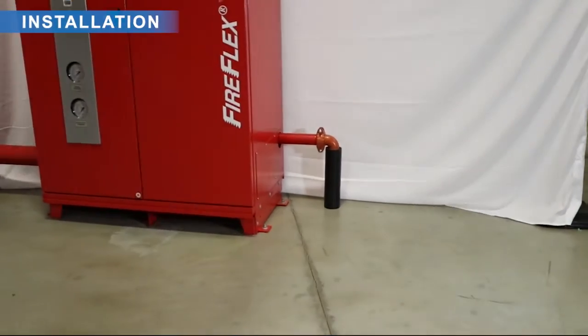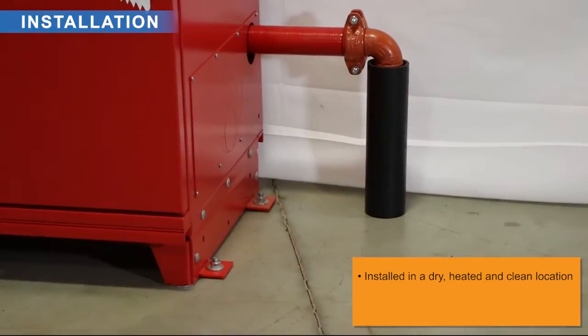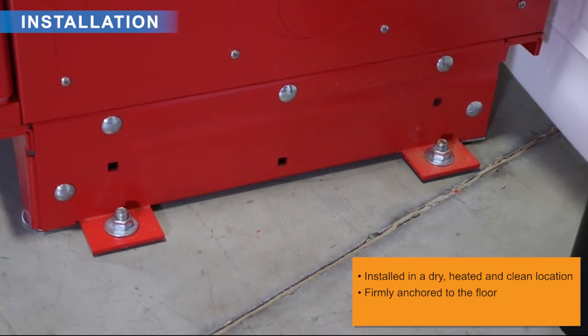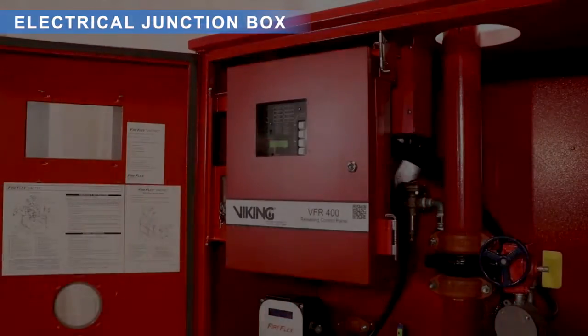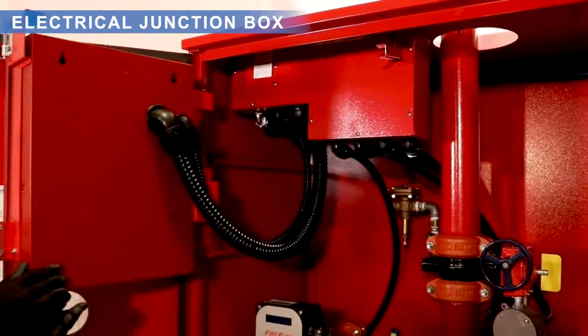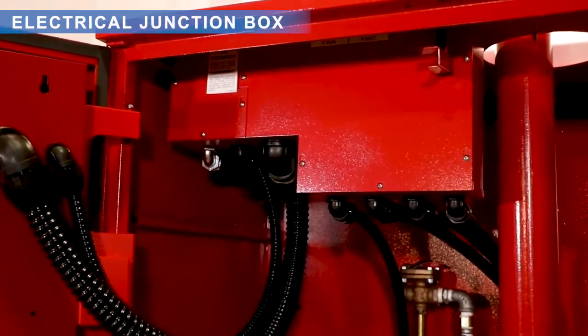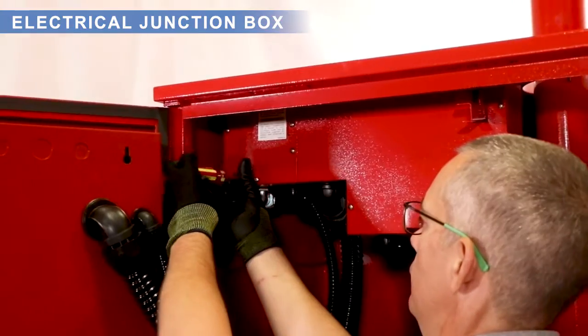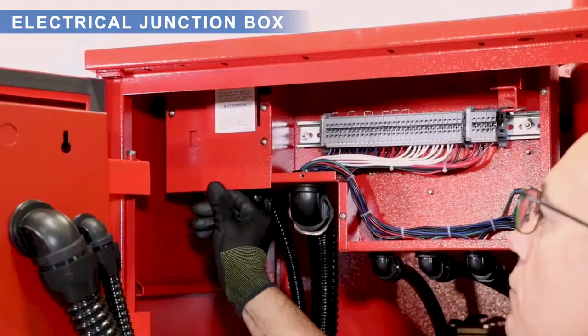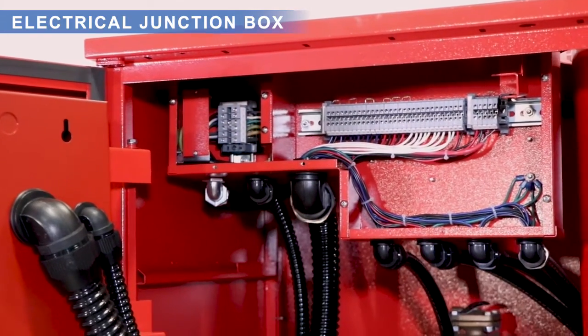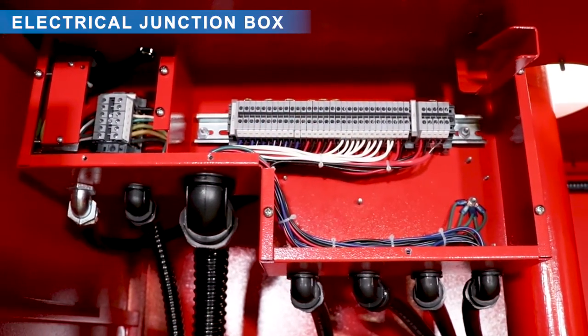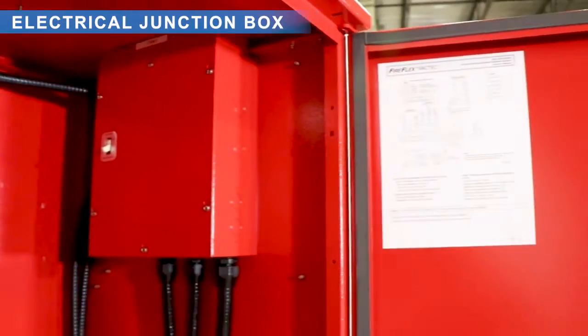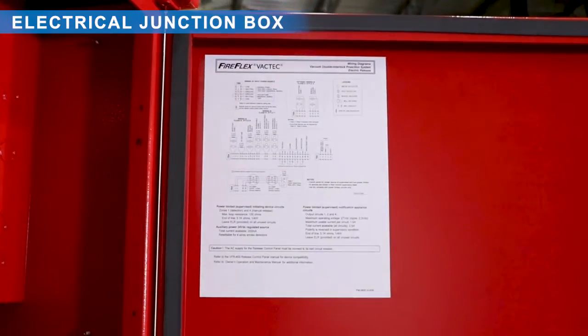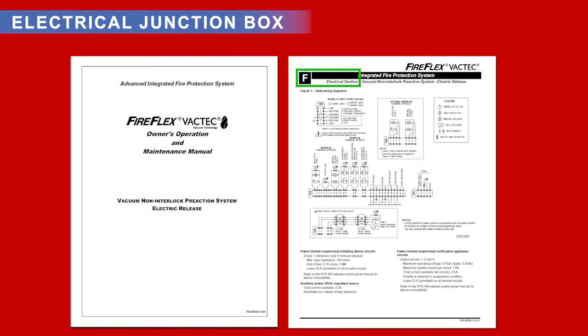Make sure that the FireFlex Vactec unit is installed in a dry, heated, and clean location, firmly anchored to the floor, and piped to an open drain. Open the electrical junction box inside the unit located behind the Viking VFR 400 panel to ensure that all detection and alarm audible devices are connected according to electrical wiring diagrams. Refer to the adhesive labels inside the main door of the Vactec unit or the electrical section of your operation manual.